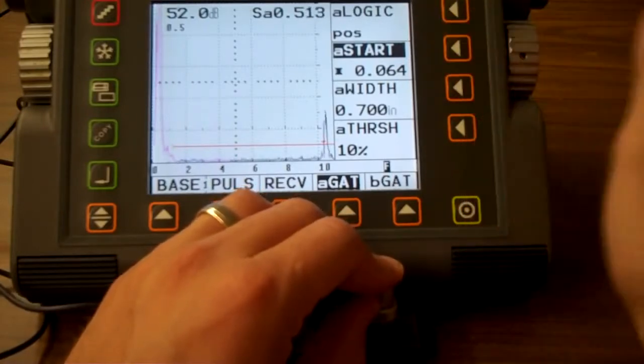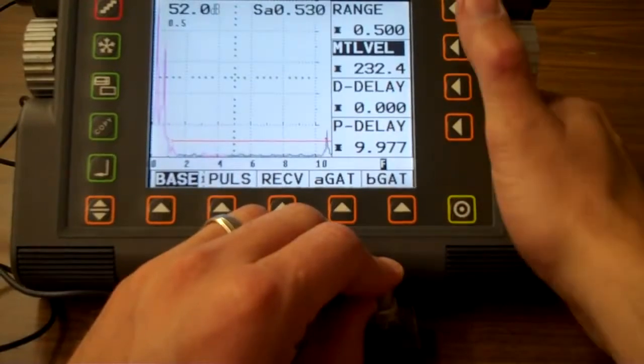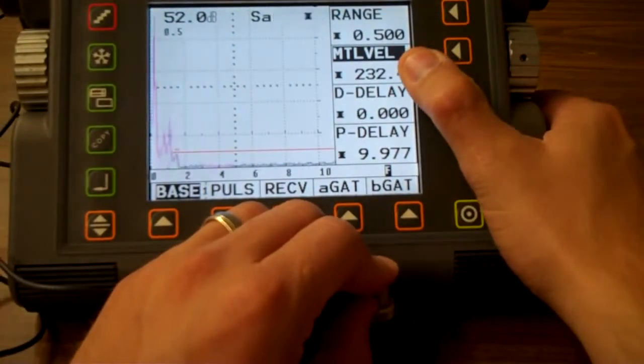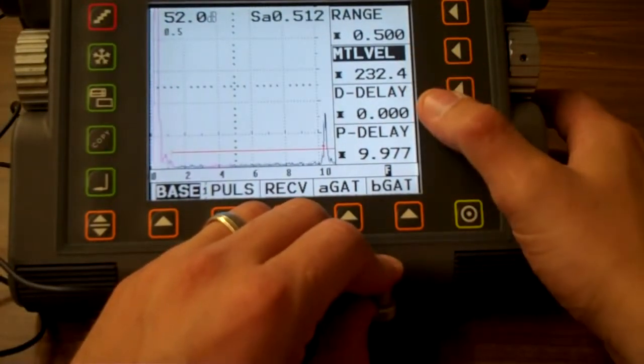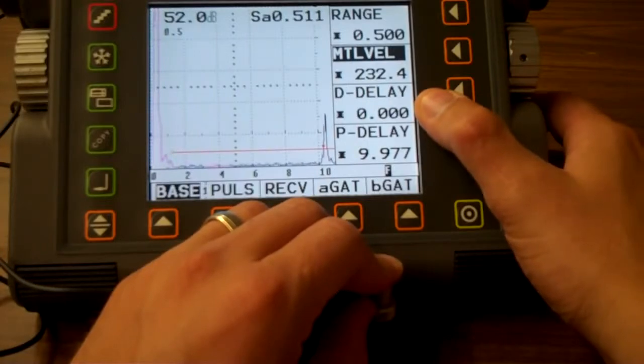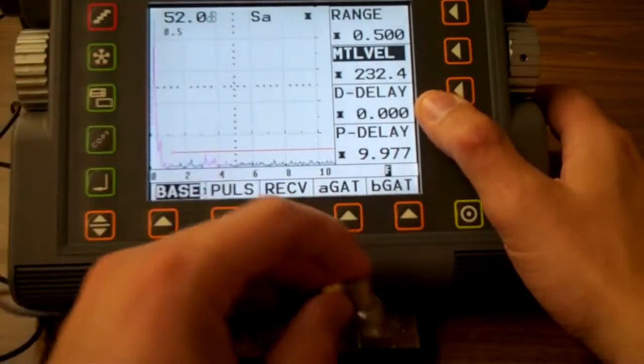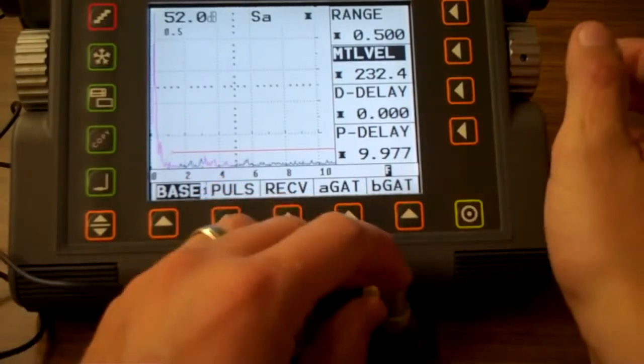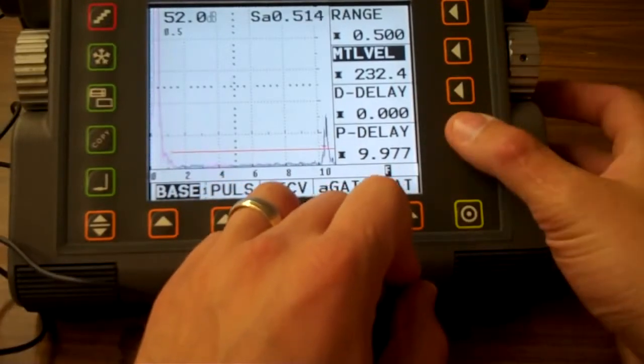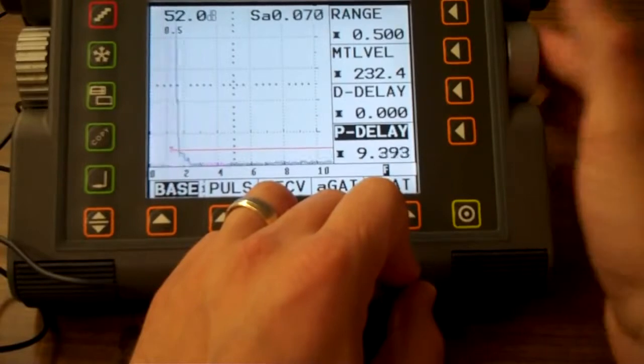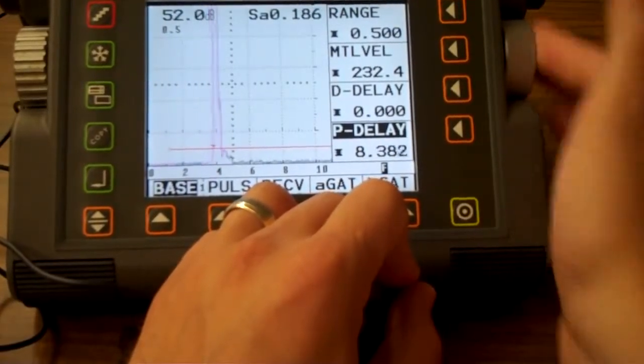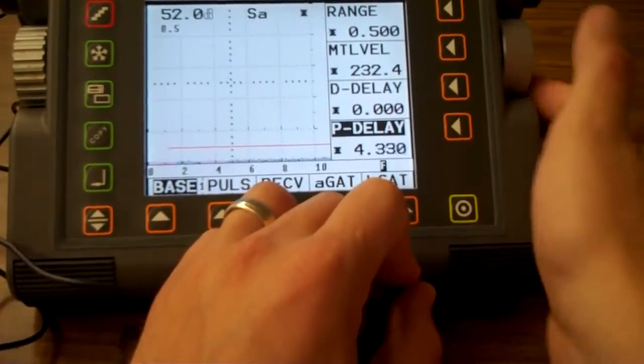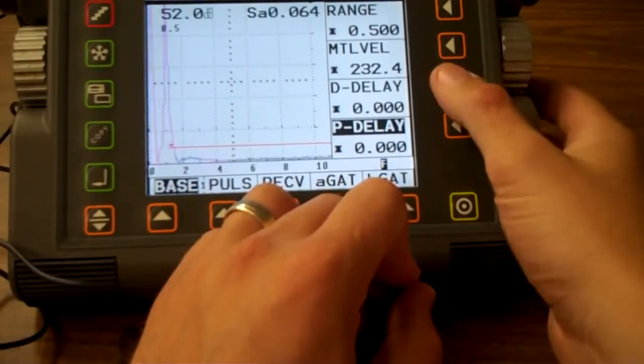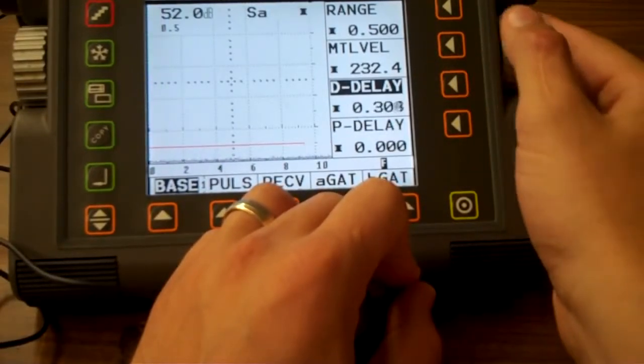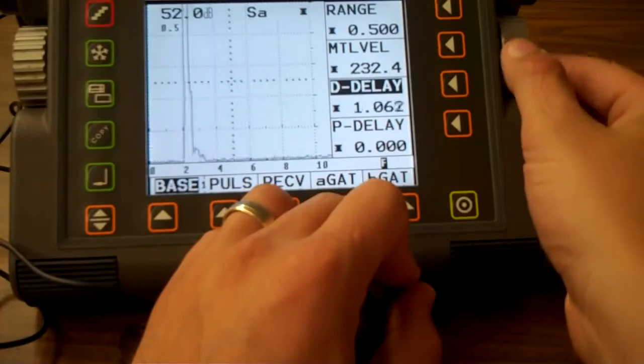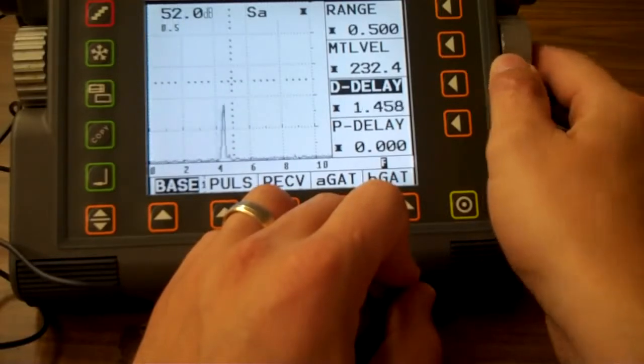So anyway, positive gate, I go back to my base menu. 1/2 inch range, that's steel. Doesn't matter if it was aluminum, I could just change my velocity. Display delay I don't want to use right now because I actually have a delay line built in, so that's important. Probe delay pushes that out and actually changes my signal. So if I just, for kicks and grins, looked at that, rolled this guy back to 0, right now I have not a very clean signal, but that moves everything, even my gate. So that doesn't do me any good.